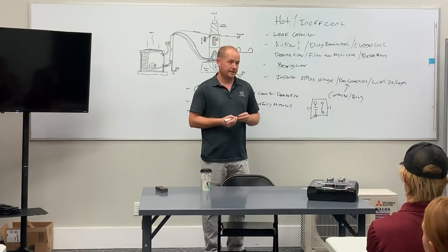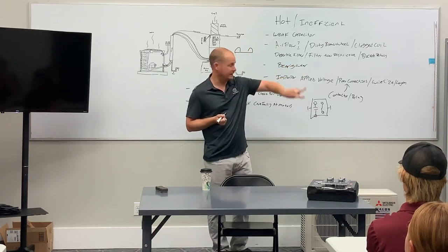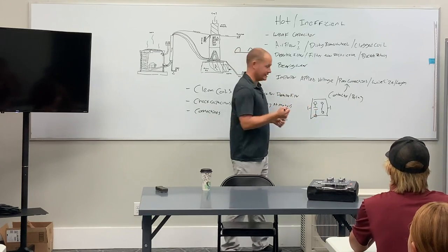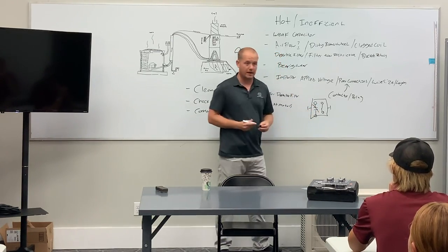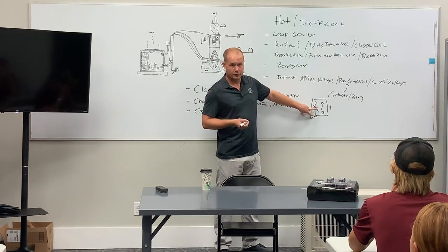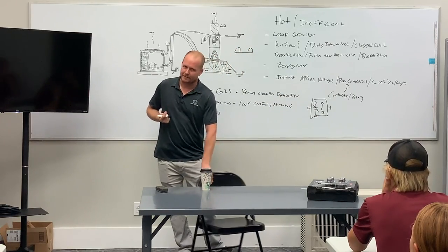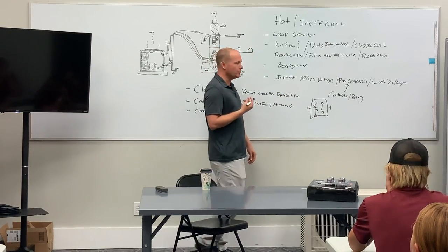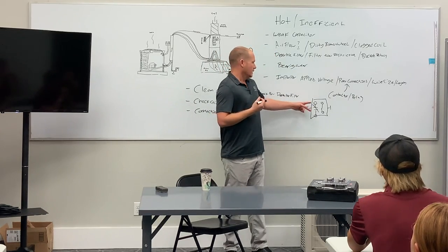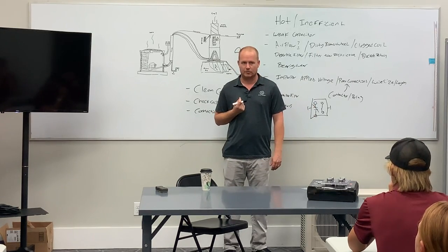You can check for voltage drop while the system's running by taking your meter leads and going across that set of contacts. When that set of contacts is closed, meaning the unit is running, there should be next to no voltage drop across that. The problem is that even in millivolts, that's a problem. If you see a volt or more, yeah, definitely a problem. But the challenge is that there's no standard of exactly what is acceptable or unacceptable.